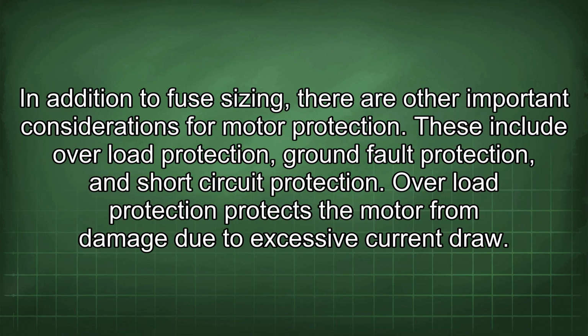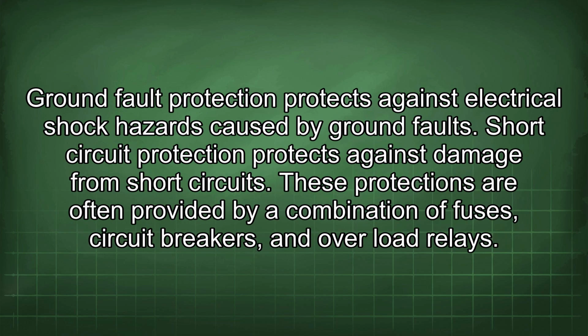In addition to fuse sizing, there are other important considerations for motor protection. These include overload protection, ground fault protection, and short-circuit protection. Overload protection protects the motor from damage due to excessive current draw. Ground fault protection protects against electrical shock hazards caused by ground faults. Short-circuit protection protects against damage from short circuits. These protections are often provided by a combination of fuses, circuit breakers, and overload relays.